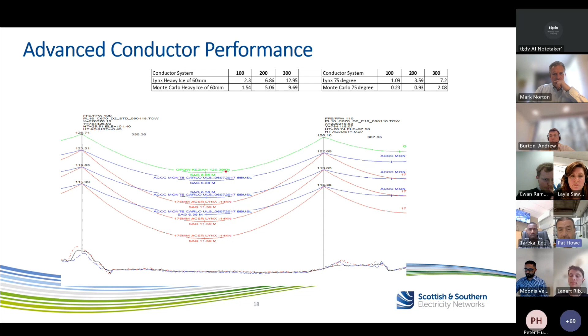So, progress on how the project's gone today. Effectively, it's been in operation since 2018 and 19, and we've not had any issues with it whatsoever. We only needed to change 3% of the towers over the route. We had 155 towers, and we only needed to change 5 to accommodate both the new conductor and the additional clearance. We had a canal to go over, so we needed the additional clearance for masts for boats, for example. So it's worked out really, really well.